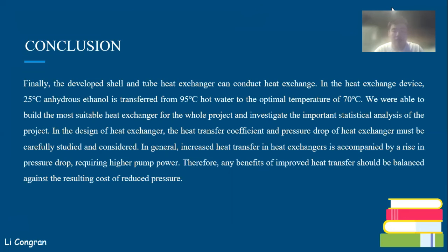In general, increased heat transfer in the heat exchanger is accompanied by a rise in pressure drop, requiring higher pump power. Therefore, any benefits of improved heat exchanger heat transfer should be balanced against the resulting cost of increased pressure drop.